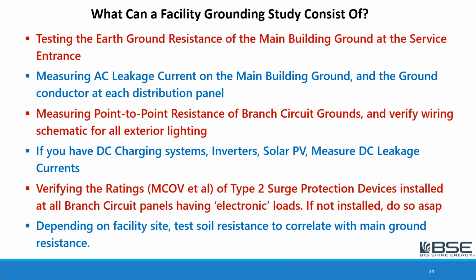But the amount of leakage current should be fairly small, in the few hundred milliamp range typically. But if you see a big number, like over 1 ampere, something's probably wrong. It may mean there's a wiring mistake or incorrect wiring connection somewhere in the building, typically a neutral to ground connection where there shouldn't be.